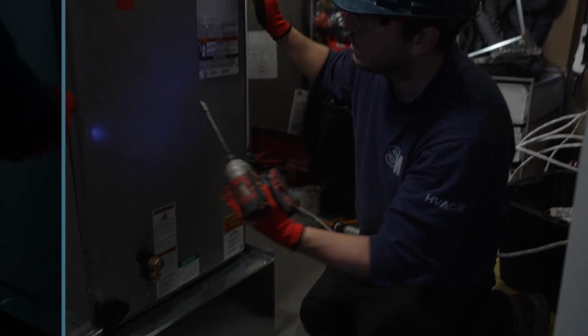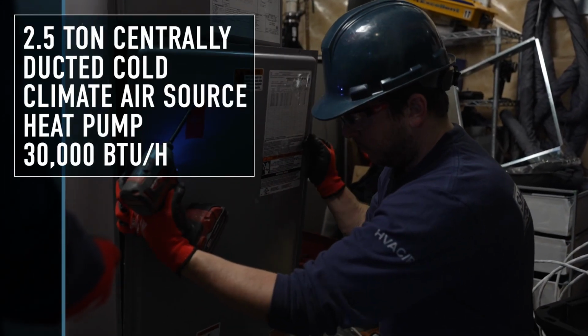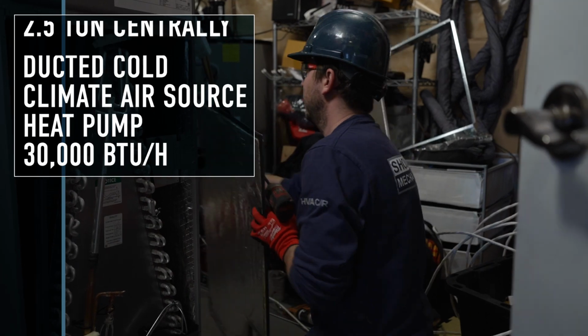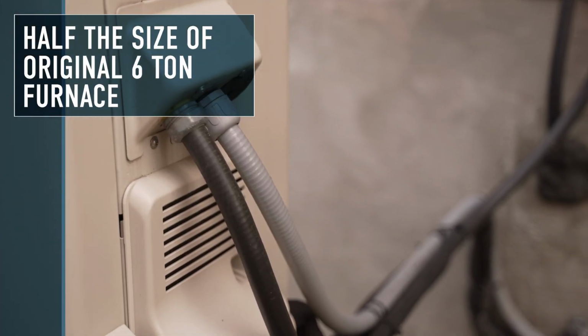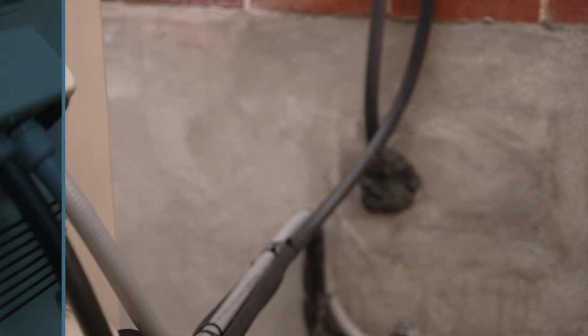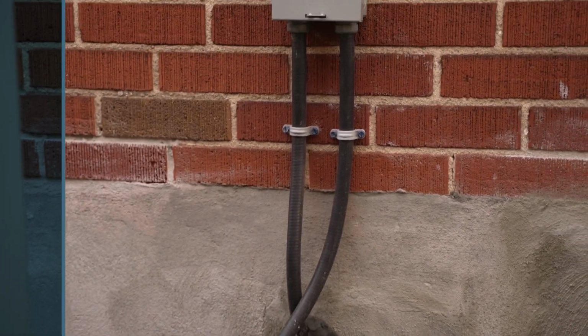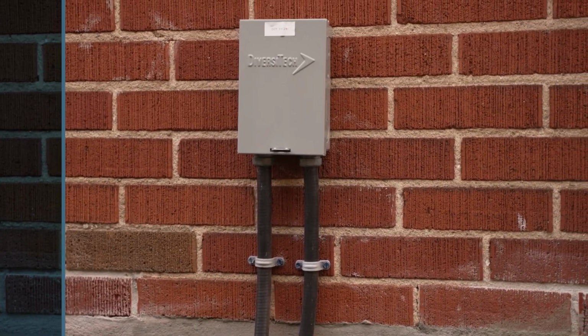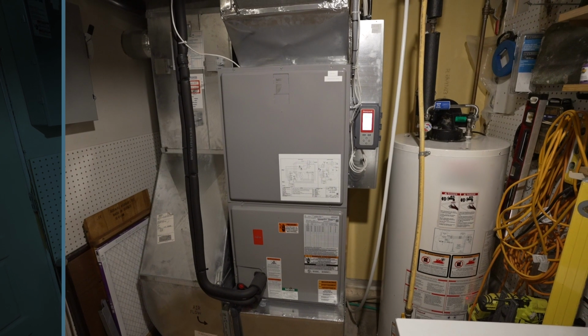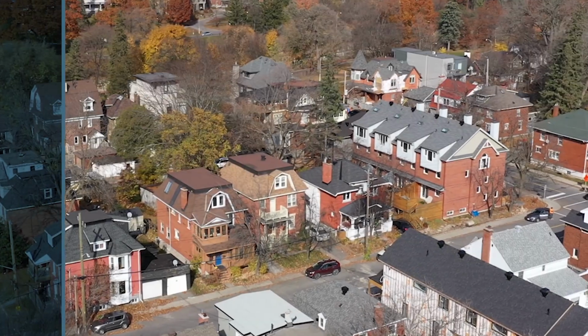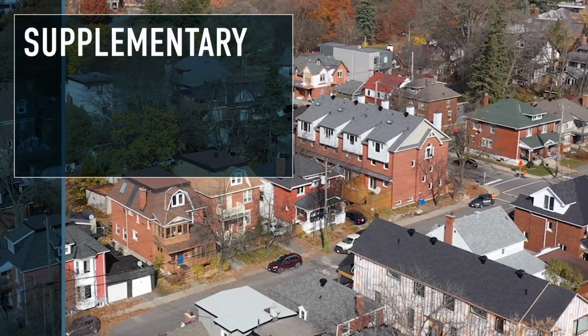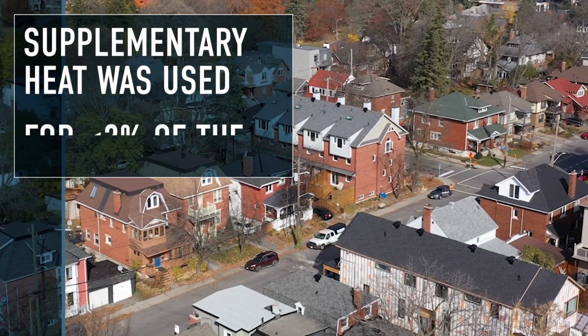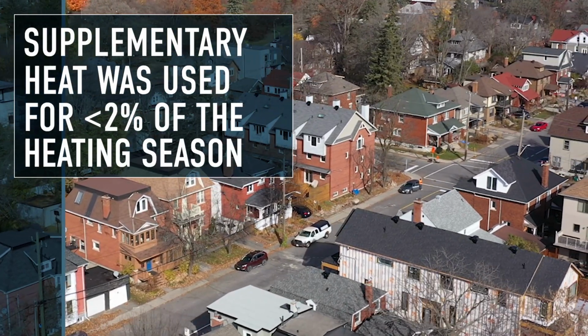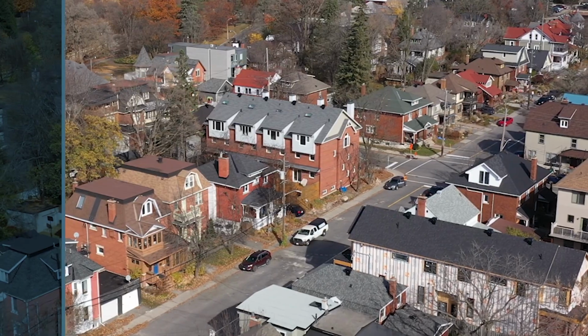In this home, we installed a 2.5-ton centrally ducted unit. That's less than half the size of the original furnace that was replaced. From monitoring the system continuously for the past year, we've seen no impacts to home comfort levels or system performance. The post-project measurements showed that the supplementary backup heating used 2% of the overall heat pump energy, and this was much less than we had expected.